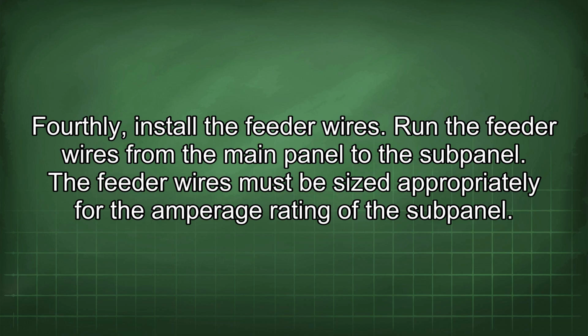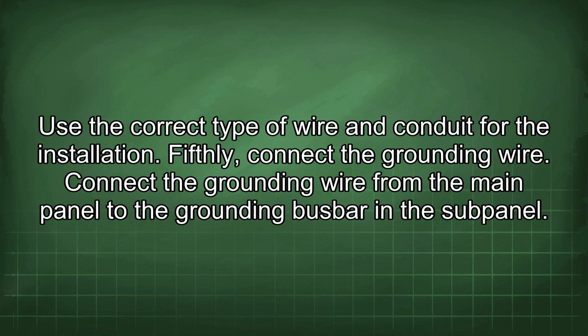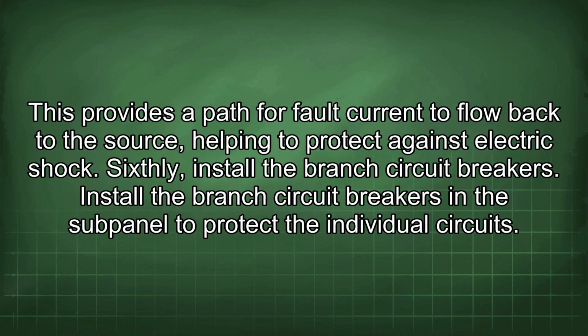Fourthly, install the feeder wires. Run the feeder wires from the main panel to the sub-panel. The feeder wires must be sized appropriately for the amperage rating of the sub-panel. Use the correct type of wire and conduit for the installation. Fifthly, connect the grounding wire. Connect the grounding wire from the main panel to the grounding busbar in the sub-panel. This provides a path for fault current to flow back to the source, helping to protect against electric shock.